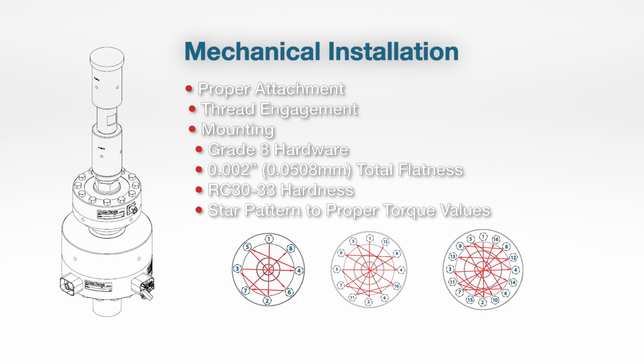If you're getting a load cell with a base, it's going to have a plug inside there, so we usually recommend threading in to where the stud bottoms out and then backing it off half to a turn just to make sure that it's not pushing on that plug. But at that point, you're going to ensure that you've got good thread engagement. The next step that we do for calibration, and again to get the best performance, is we would attempt to preload the load cell. So we would actually put a tension load on it to about 130% of capacity and lightly jam the jam nut.